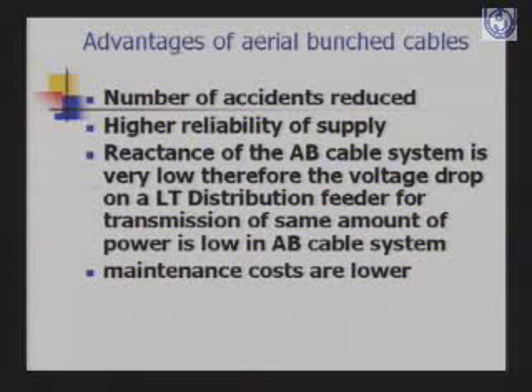The number of accidents are reduced, you have higher reliability of supply, and reactance of the AB cable system is very low. Therefore, voltage drop on a LT distribution feeder for transmission of same amount of power is low in aerial bunched cable system. When voltage drop is less, your losses will also be lower, and the maintenance costs are much lower.